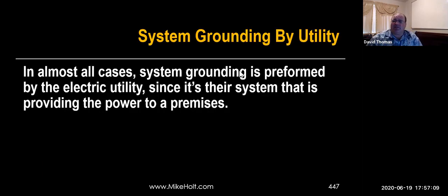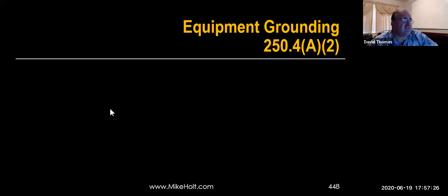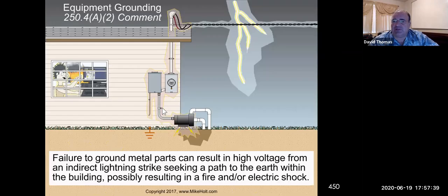So in almost all cases, system grounding is performed, not preformed, by the electric utility, since it's their system that provides the power to the premise. And that's true, but in our transformers we do the same thing. We create a separate system inside the building, and so it's important that we actually understand this. At least I do a lot of it, in commercial and industrial type applications.